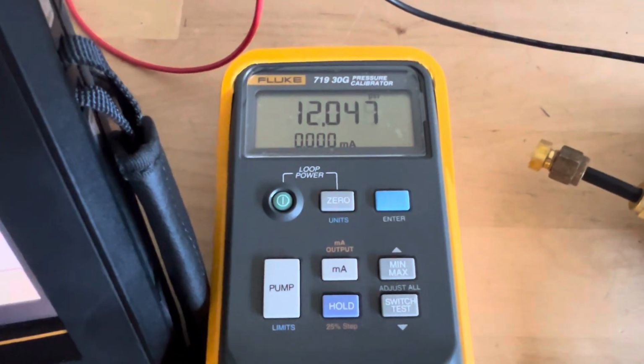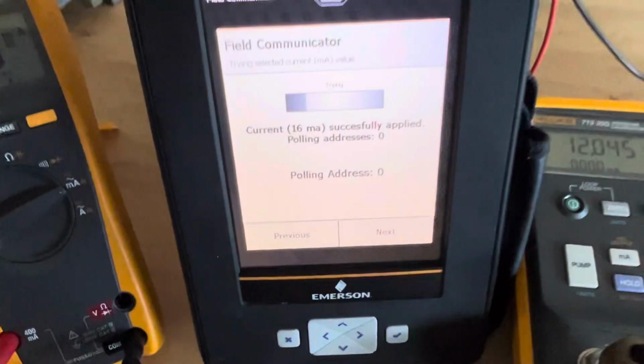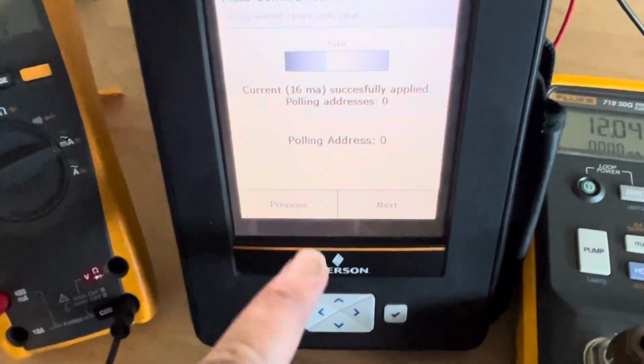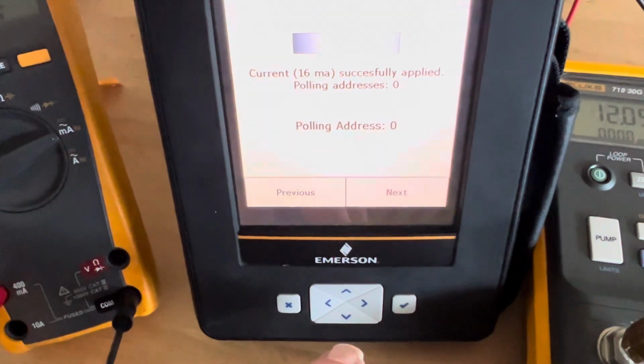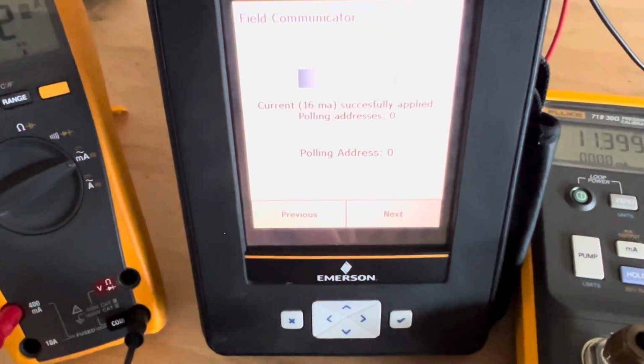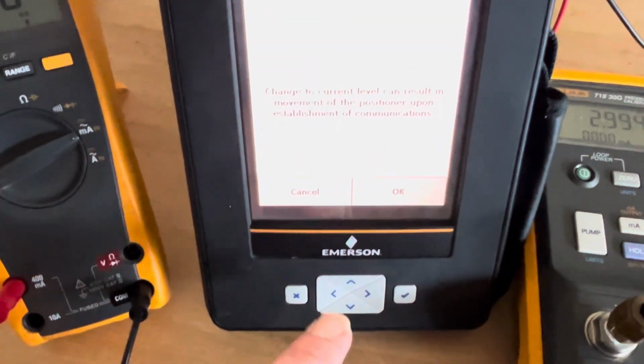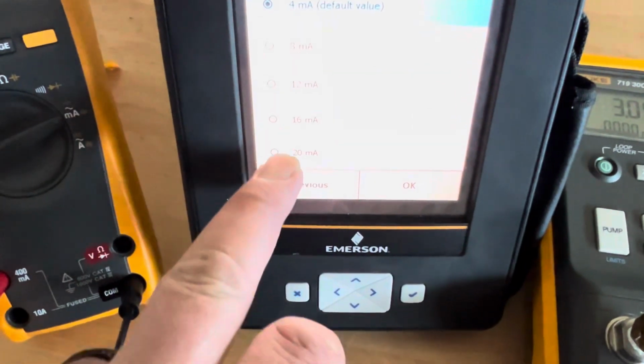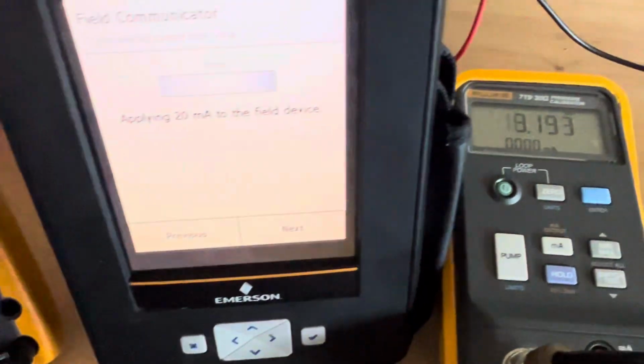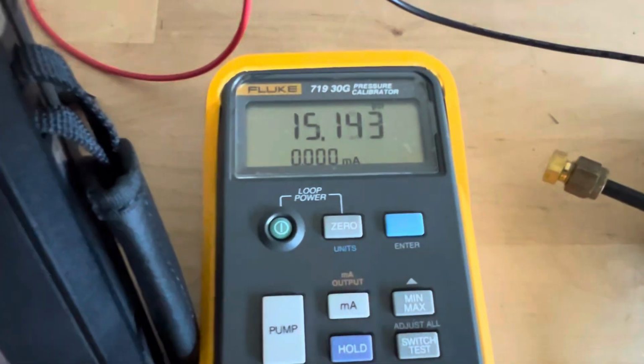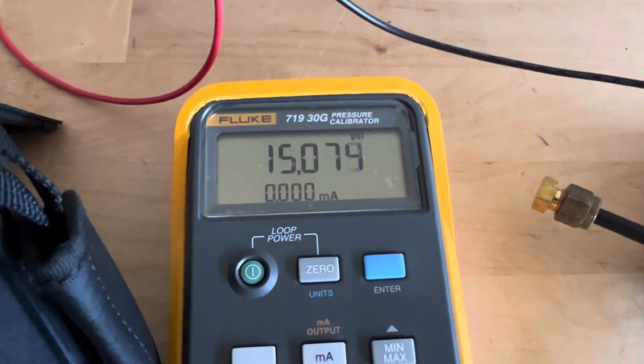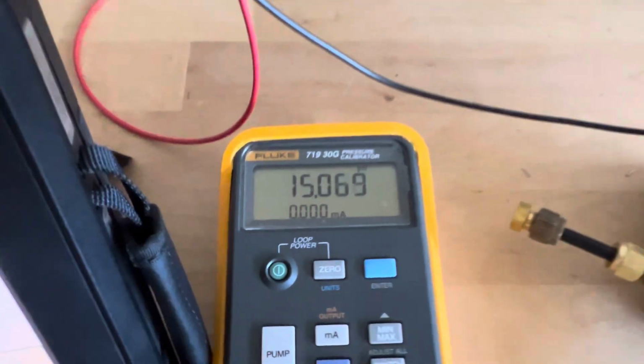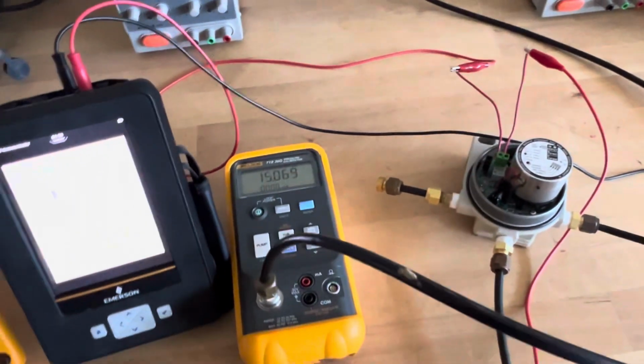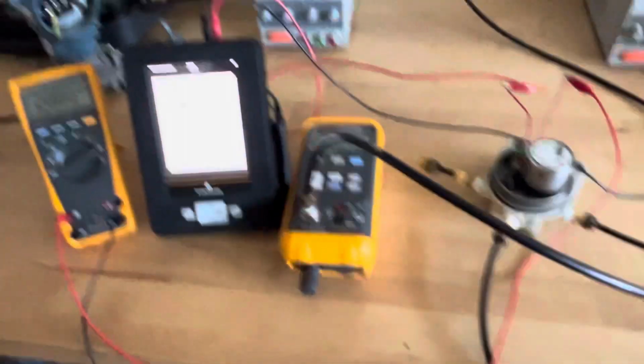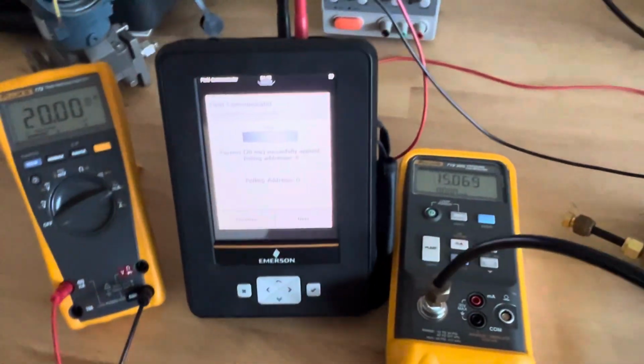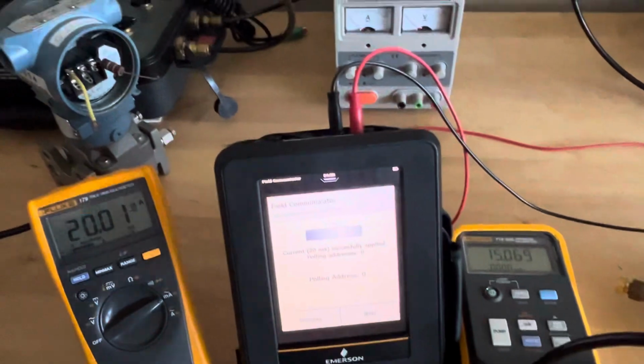Very, very good, 12.0. All right, one last time, we're going to go to our 20 milliamps. And we should get about 15 PSI. Beautiful. And that is how you calibrate an I to P transducer, supplying your 4 to 20 milliamp signal from our Trex unit.